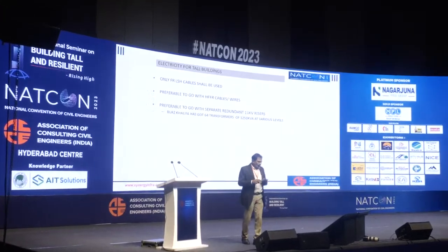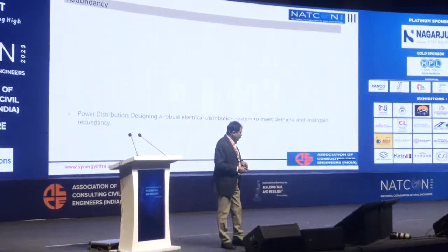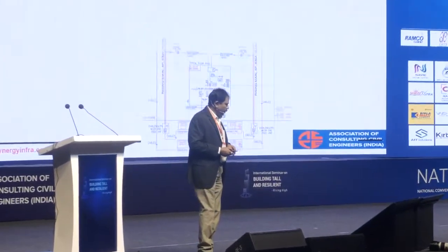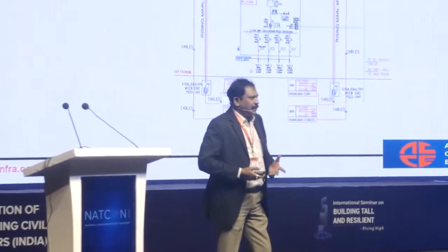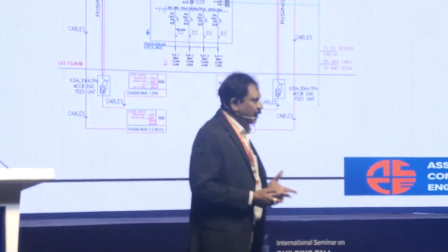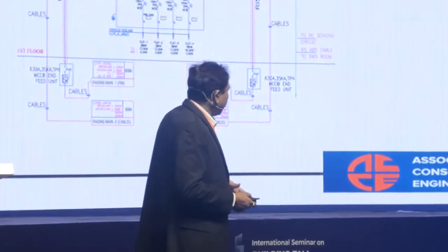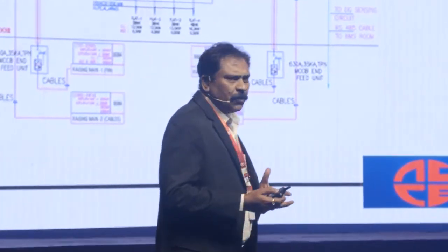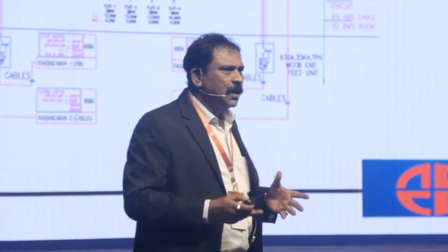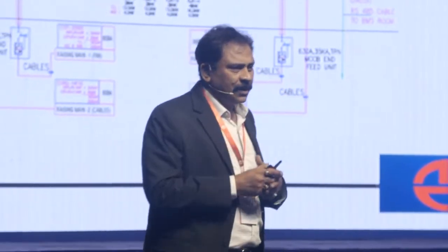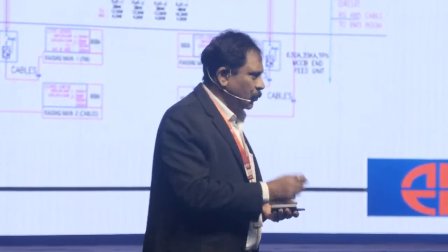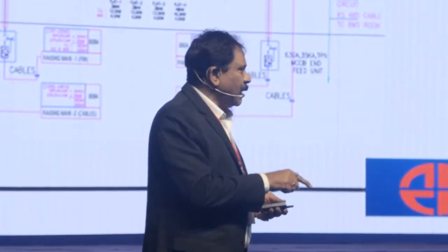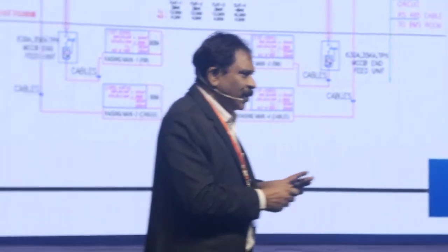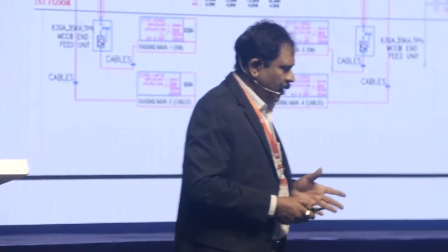Also, when we talk about high-rise buildings, I would like to show you something: we have to look at redundancy. I think this is highly essential. We can't depend on just one path. We have two ways of doing power distribution: either through cables, or through what we call a bus riser, a bus duct running through the building. Whenever the breaker trips, the whole power will go off for the whole building. So naturally we need redundancy.